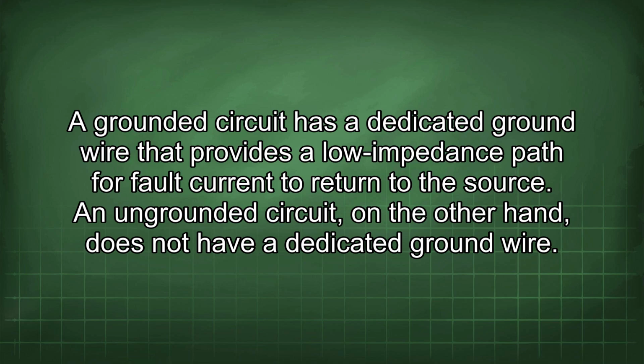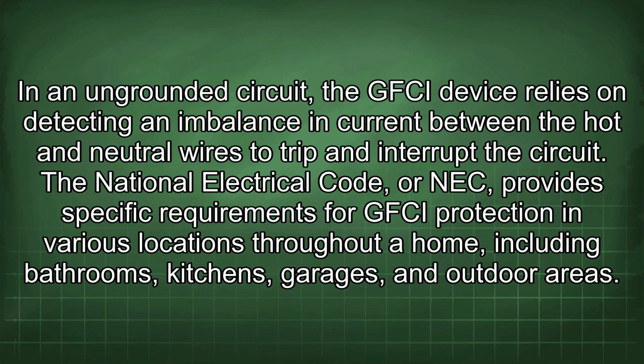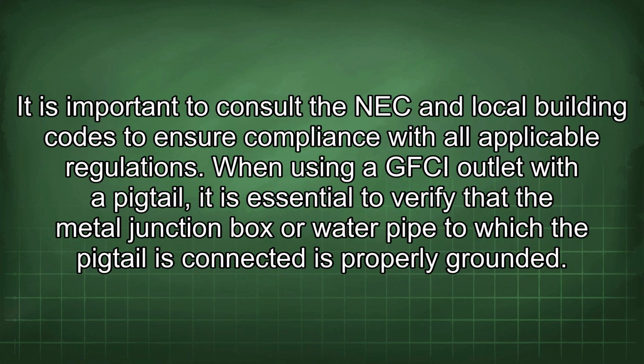An ungrounded circuit, on the other hand, does not have a dedicated ground wire. In an ungrounded circuit, the GFCI device relies on detecting an imbalance in current between the hot and neutral wires to trip and interrupt the circuit. The National Electrical Code, or NEC, provides specific requirements for GFCI protection in various locations throughout the home, including bathrooms, kitchens, garages, and outdoor areas. It is important to consult the NEC and local building codes to ensure compliance with all applicable regulations.